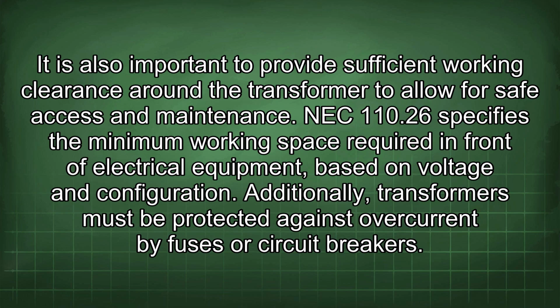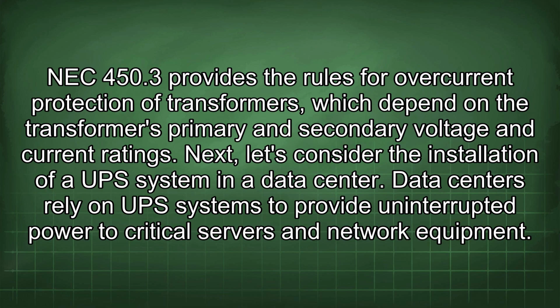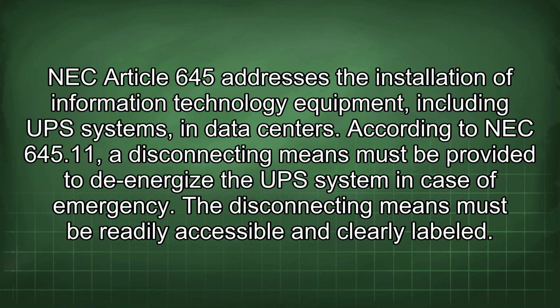NEC 110.26 specifies the minimum working space required in front of electrical equipment based on voltage and configuration. Additionally, transformers must be protected against overcurrent by fuses or circuit breakers. NEC 450.3 provides the rules for overcurrent protection of transformers, which depend on the transformer's primary and secondary voltage and current ratings. Next, let's consider the installation of a UPS system in a data center. Data centers rely on UPS systems to provide uninterrupted power to critical servers and network equipment. NEC Article 645 addresses the installation of information technology equipment, including UPS systems, in data centers.